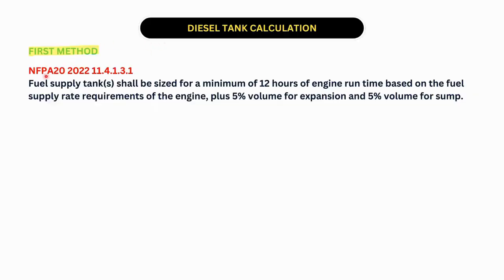I will now read what NFPA states about Method 1 for selecting diesel tank size. As per NFPA 20 edition 2022, the fuel supply tank shall be sized for a minimum of 12 hours of engine run time, based on fuel supply rate requirements of the engine, plus 5% volume for expansion and 5% volume for sump. We will understand this point in the next slide.